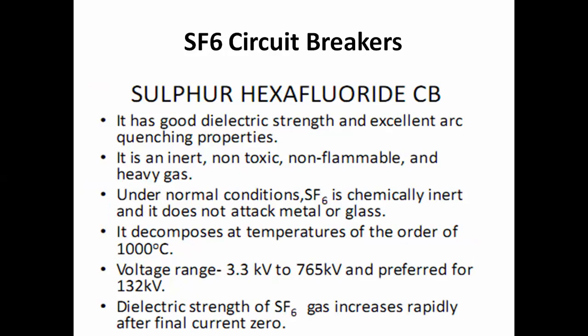as we all know, we have discussed the various classifications of the circuit breaker, and the classification is based upon the arc quenching media we use. Like in the case of a minimum oil circuit breaker or an oil circuit breaker, we use oil as the arc quenching media to extinguish the arc. Whereas in the case of the air blast circuit breaker, we use a blast of air to quench the arc. In the same way, if you quench the arc with the help of a gas, then that circuit breaker is called an SF6 circuit breaker.